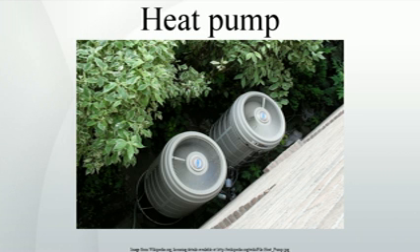The heat drawn from ground-sourced systems is in most cases stored solar heat, and it should not be confused with direct geothermal heating, though the latter will contribute in some small measure to all heat in the ground. True geothermal heat, when used for heating, requires a circulation pump but no heat pump, since for this technology the ground temperature is higher than that of the space that is to be heated, so the technology relies only upon simple heat convection.